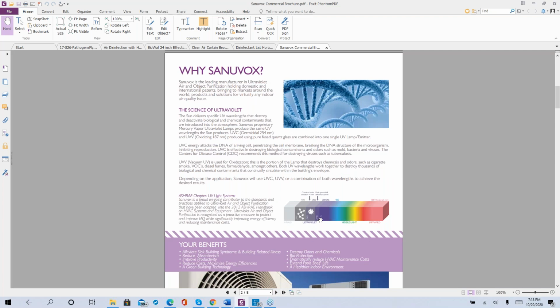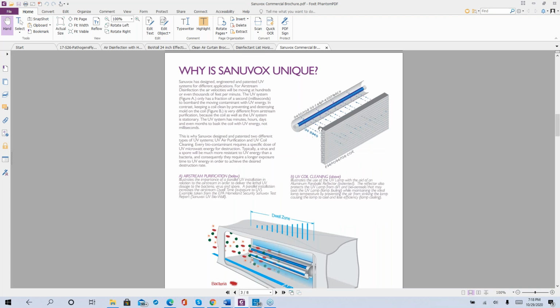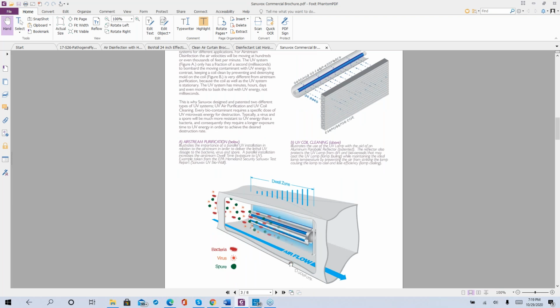We've talked about the UV light, and actually they are listing ASHRAE. And here's the coil cleaning against it. But the interesting fact is that you're getting your 99% this way, but if you're mounting this way, you're shining on the coil only. And of course, you can see that as the airflow is coming across, it's being blocked by the parabolic reflector that's further shining and intensifying the UV light. So you will irradiate some of the airflow, but you're only getting about a 40% kill rate. Now you can still get to the 99% by multiple passes, but the better part is to mount it the way that the manufacturer indicates with the airflow.